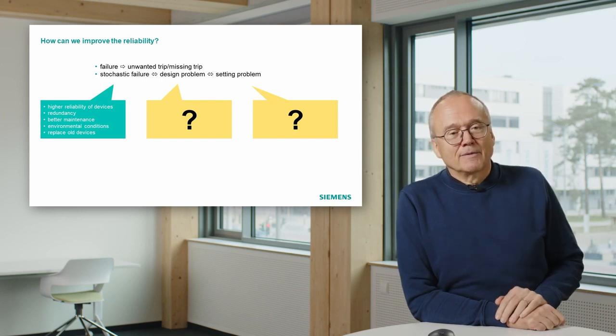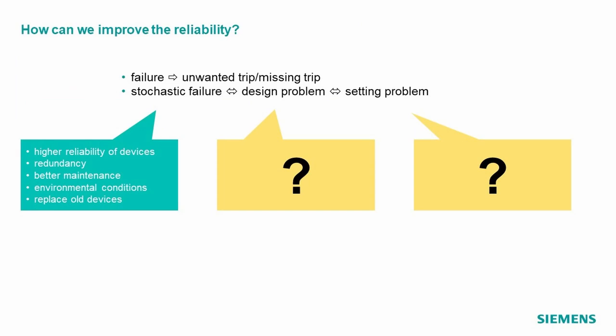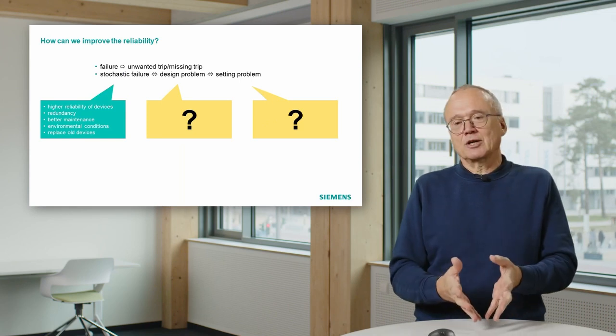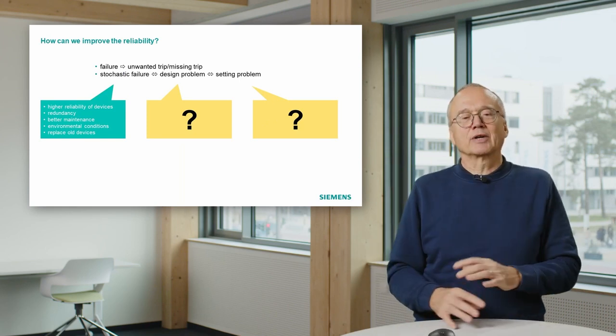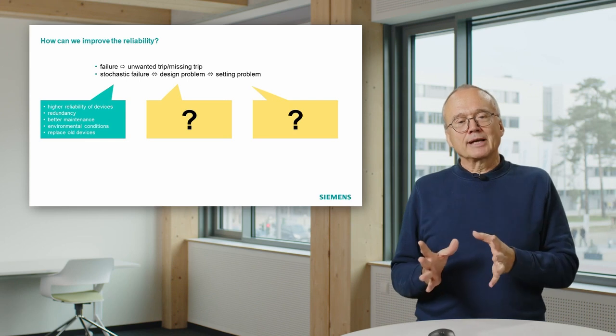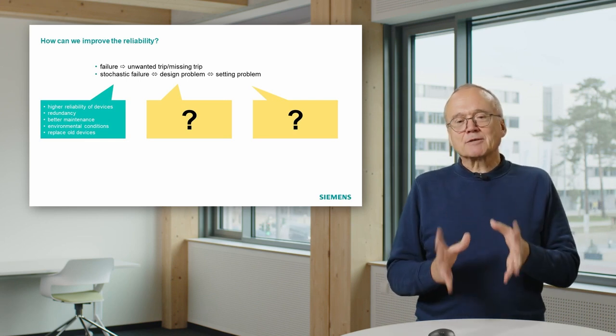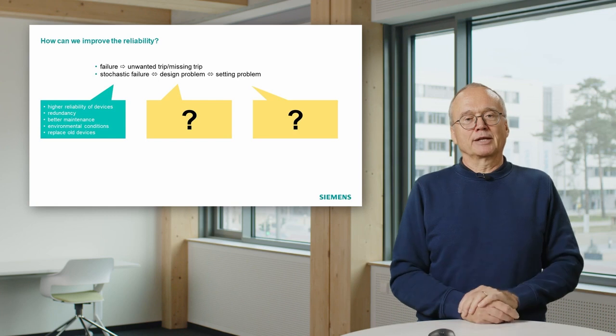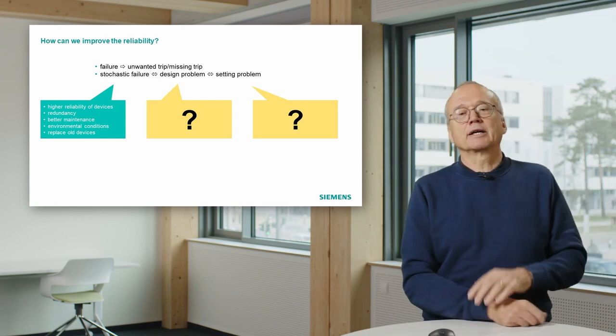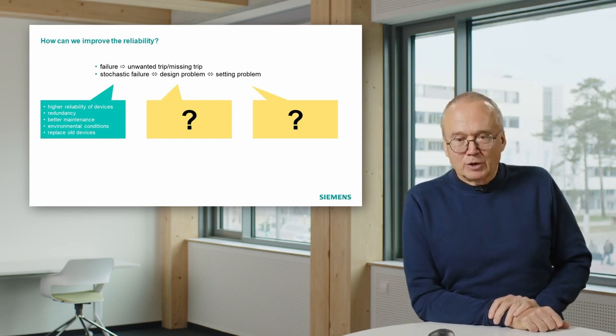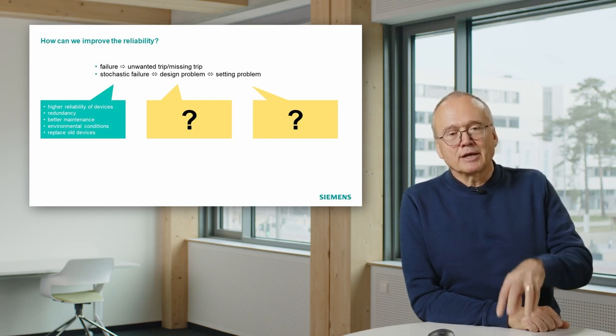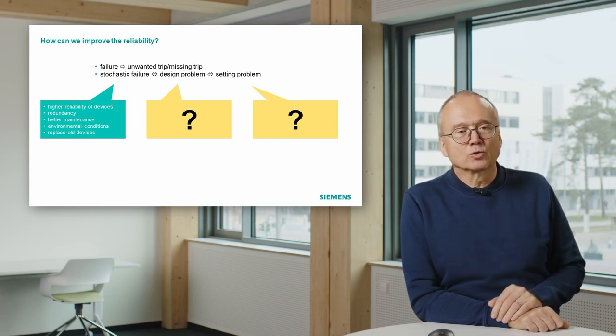Then, and that is now the question of the user of protection relays, we typically have redundancy. That means we must design our protection concept in a way that if one device fails for whatever reason, because the relay is out of order, the circuit breaker doesn't work, the wiring is damaged or whatever, if one relay doesn't work, there must be something else. There must be a backup for that. And that is an important design criterion for the protection concept. You always have to think, if this protection relay fails, who is going to do the job?